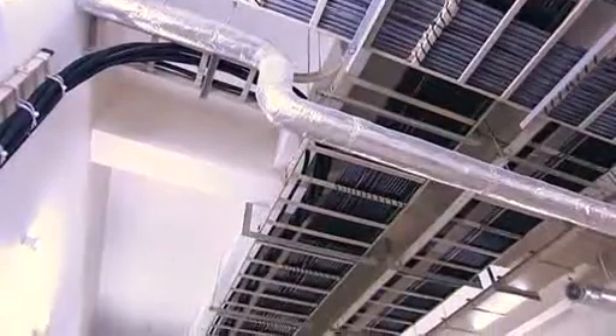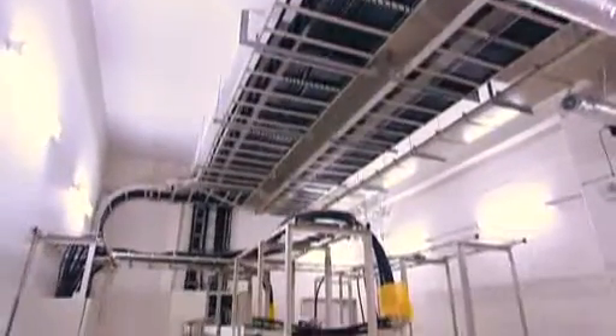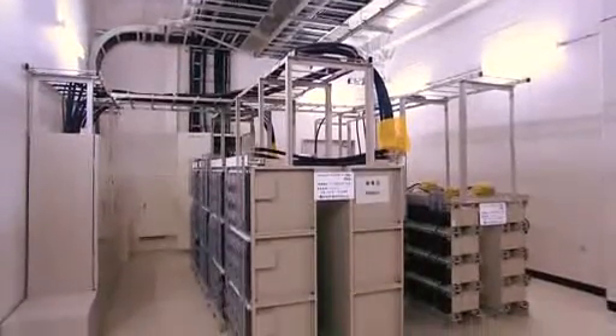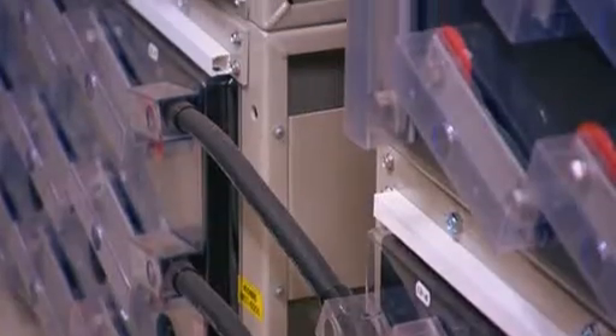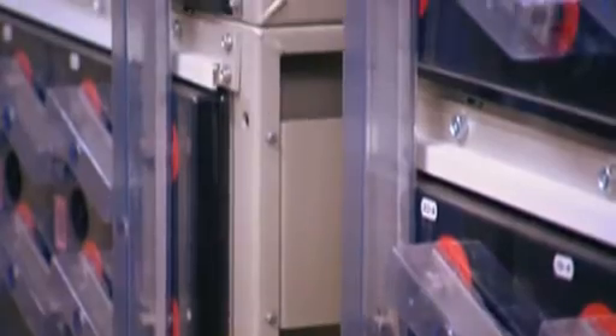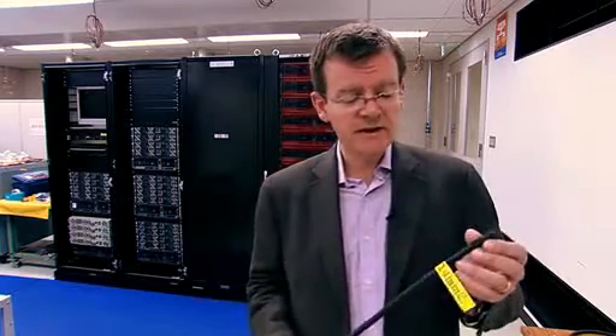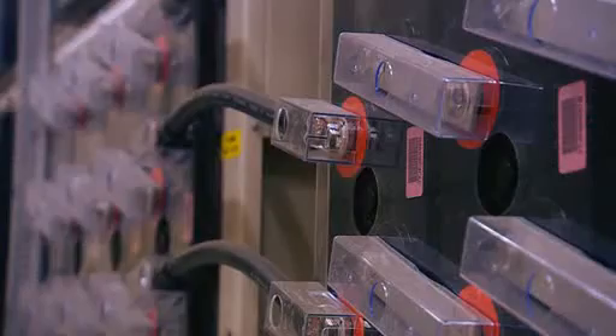Within a data centre, about 45% of mains power is used by the ICT equipment itself, such as servers, routers and storage, with 40% being used for air conditioning. These facilities rely on backup power via DC-powered batteries, and today that means 4 stages of power conversion, with up to 10% power loss at each stage. The NTT solution uses high-voltage direct current, which reduces this to 2 stages. What's more, installations can use smaller diameter cabling, which reduces installation costs.